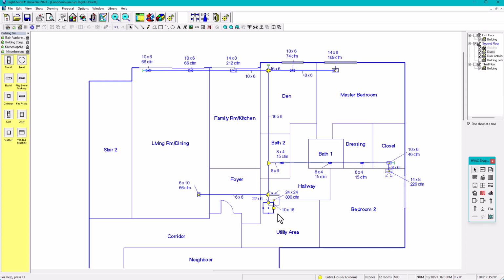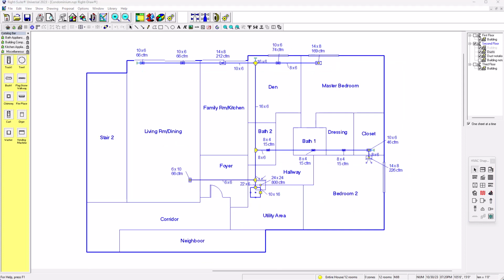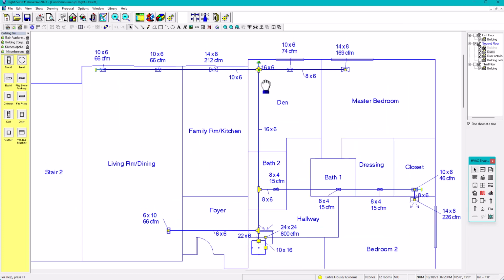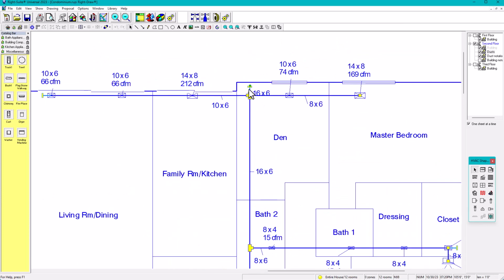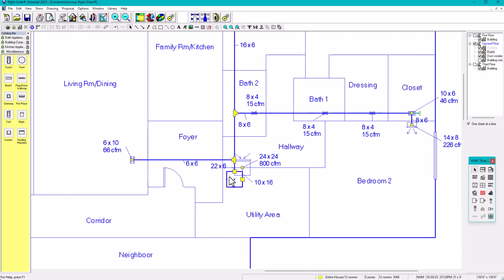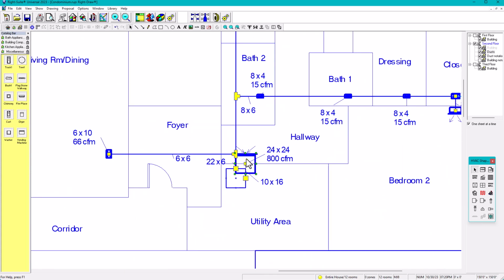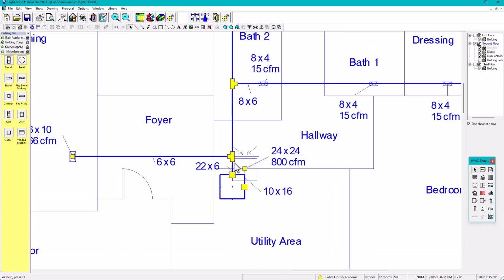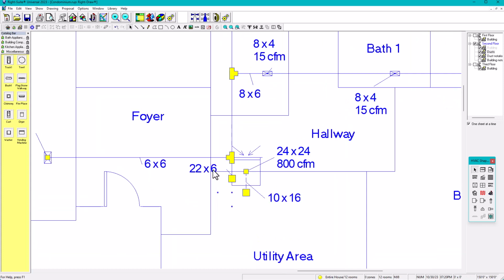It's looking better. Now is the time to analyze if our sizes are correct. Okay, so number one, let's delete this ductwork. So this duct we're not gonna need, so we can click in here, delete. All right, so now it looks more like a T, right? Okay, so now in this part, so this is very close. Let's see if I can, so this is gonna be 22 by 6. That duct doesn't seem to be very good at all.